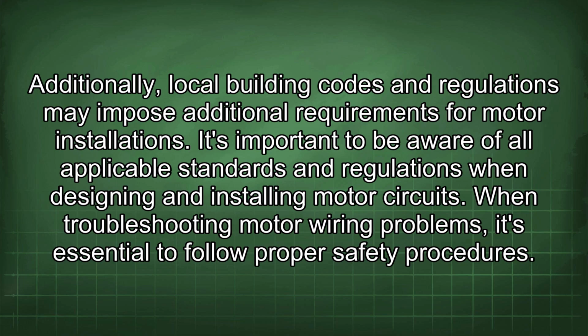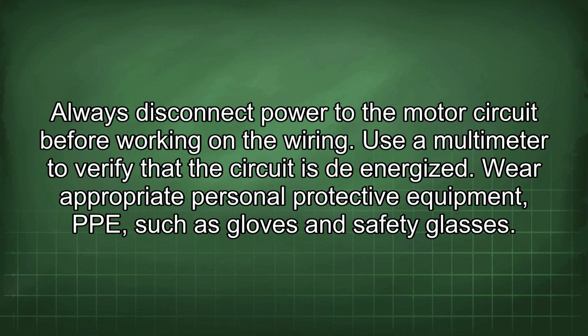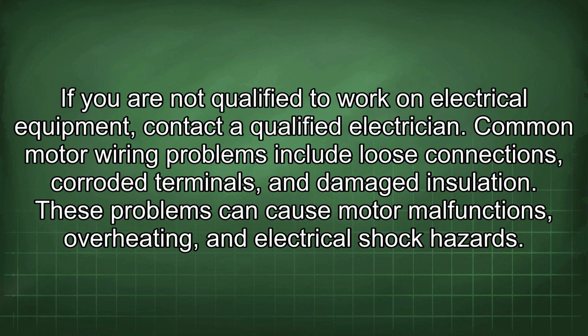When troubleshooting motor wiring problems, it's essential to follow proper safety procedures. Always disconnect power to the motor circuit before working on the wiring. Use a multimeter to verify that the circuit is de energized. Wear appropriate personal protective equipment, PPE, such as gloves and safety glasses. If you are not qualified to work on electrical equipment, contact a qualified electrician.